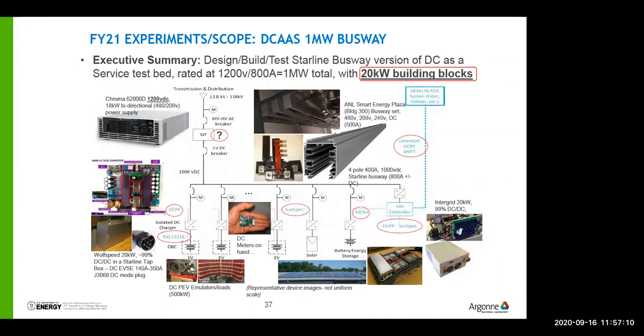In the lower left is the Starline busway tap box. These tap boxes, shown in the center, have red-coated bus bars that go into slots in the busway. This busway can hold 4-pole 400 amp, or basically 800 amps. It's rated at 1000 volts, but I can physically run it at 1200 volts, though it's only rated for 1000 per the NRTL listing. The point is, at 1200 volts and 800 amps, I can push a megawatt down this busway.